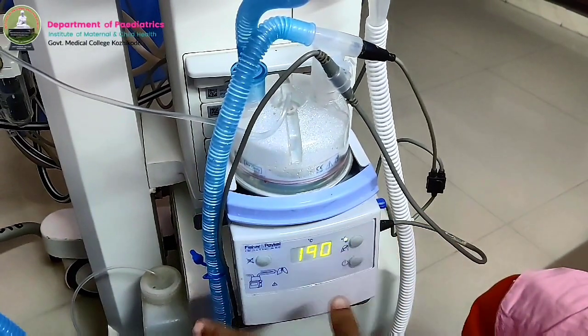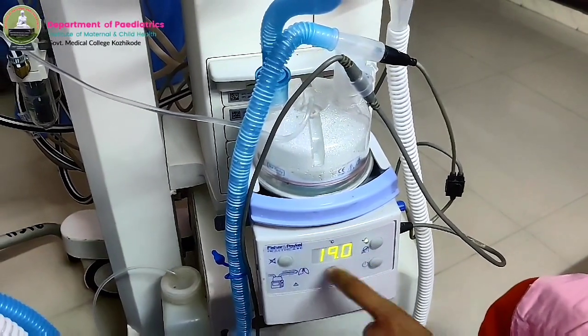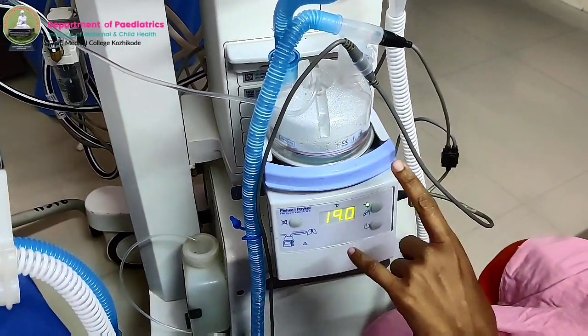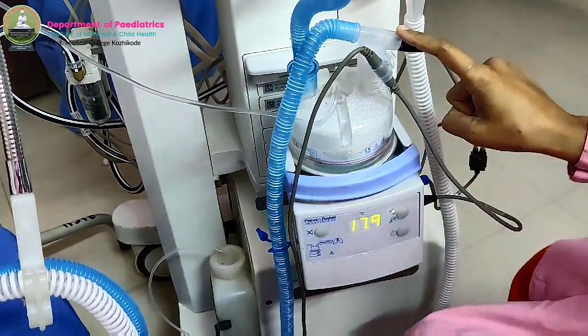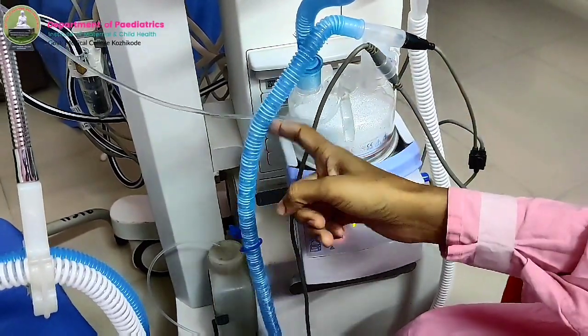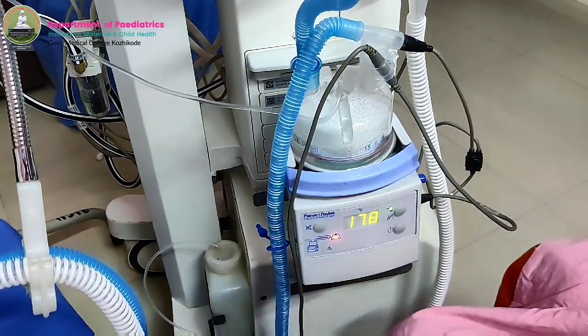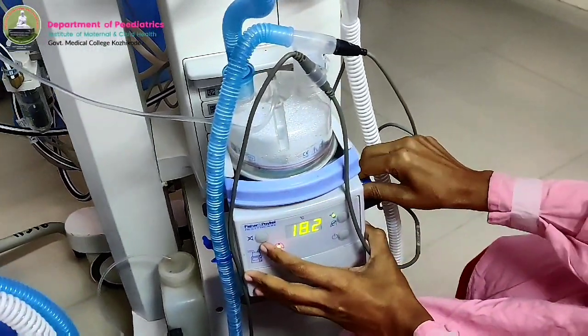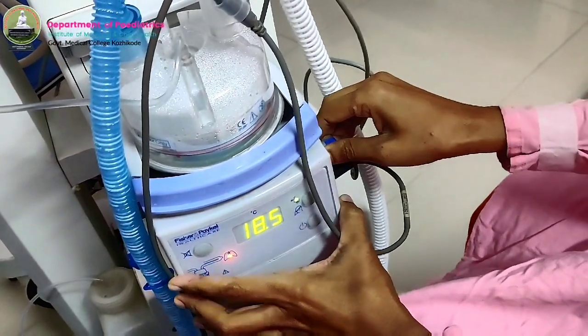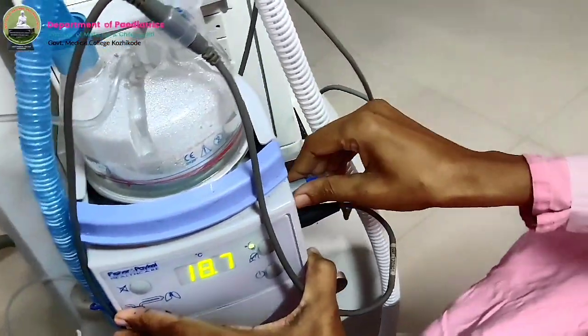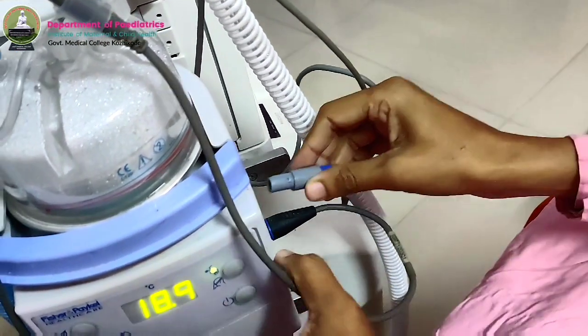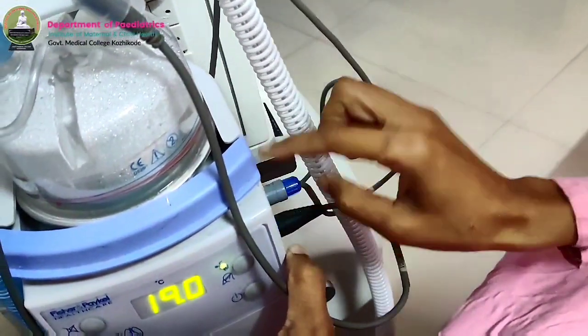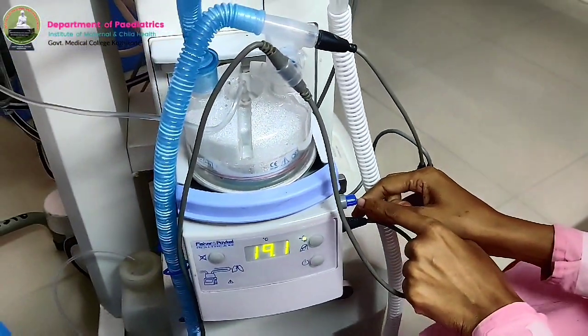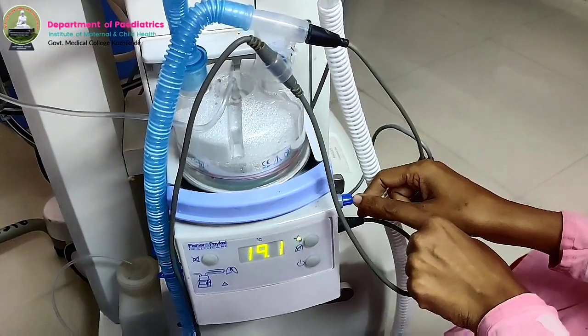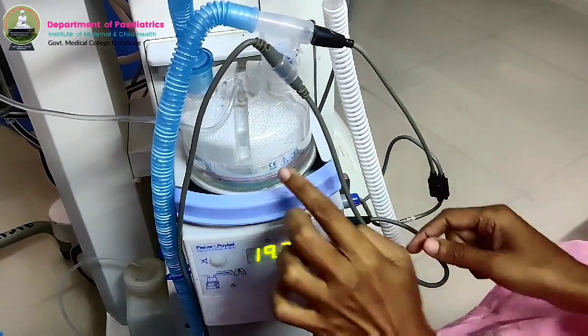So in the troubleshooting, we may get low temperature readings. In that point, always ensure whether these heating cords are properly fixed. Loose contact here causes the heater wire not getting heated up and temperature will get low. So another reason is poor connection or loose connection at this level. So by removing that, there is a wedge here and it should be properly fixed. Then only it will act. Sometimes the wire may get cracked here and loose connection can occur here also. So these are the 3 points where the temperature can get low.